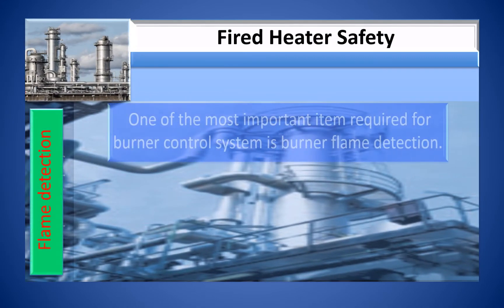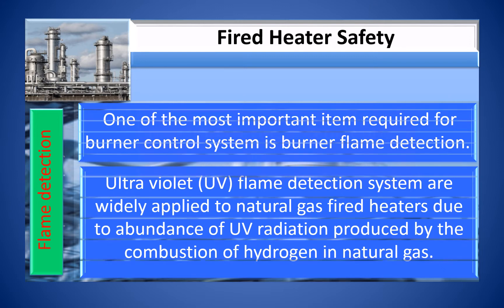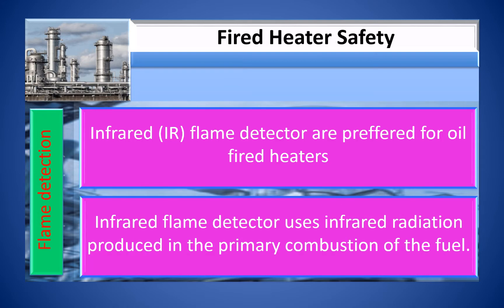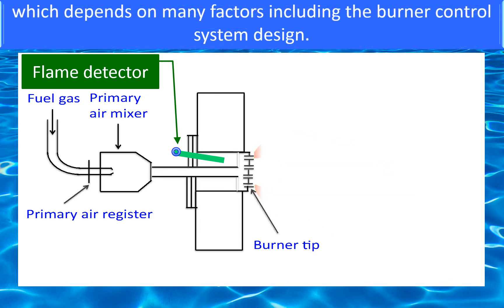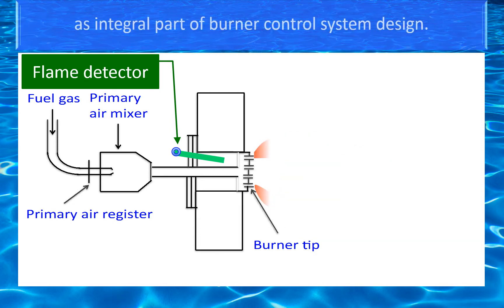One of the most important items required for burner control is flame detection. Ultraviolet UV flame detection systems are widely applied to natural gas-fired heaters due to the abundance of UV radiation produced by combustion of hydrogen in natural gas. Infrared IR flame detection is preferred for oil-fired heaters, as it uses infrared radiation produced in the primary combustion of the fuel. The proper location of the flame detector on the burner is important and depends on many factors, determined by the fired heater supplier in coordination with the BMS provider as an integral part of the burner control system design.